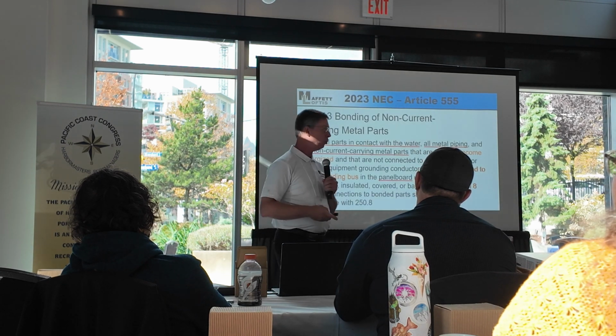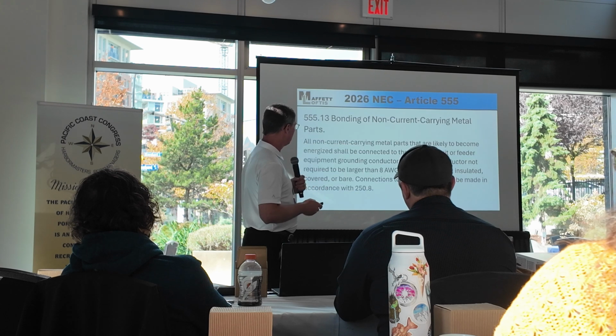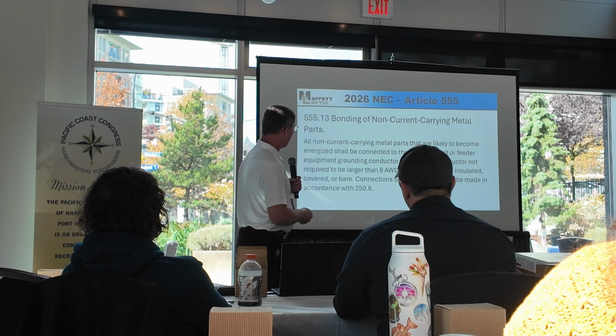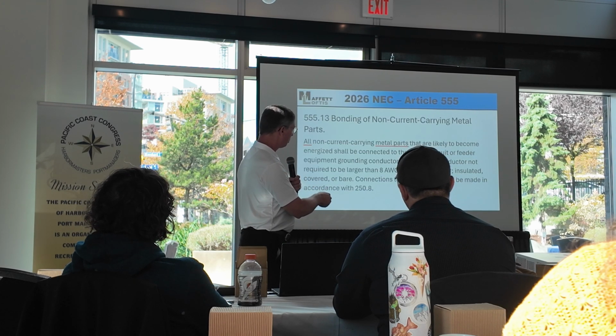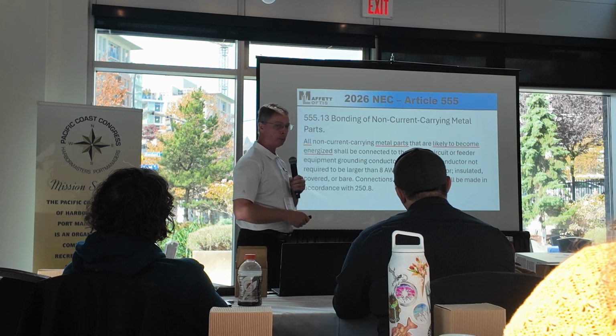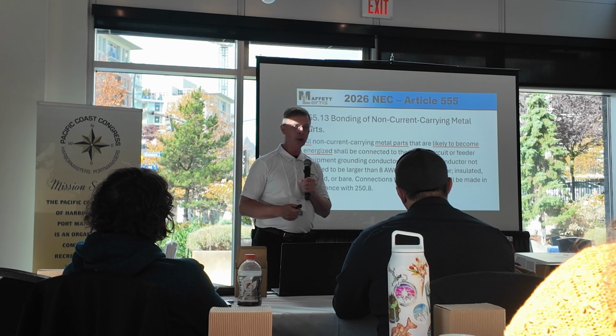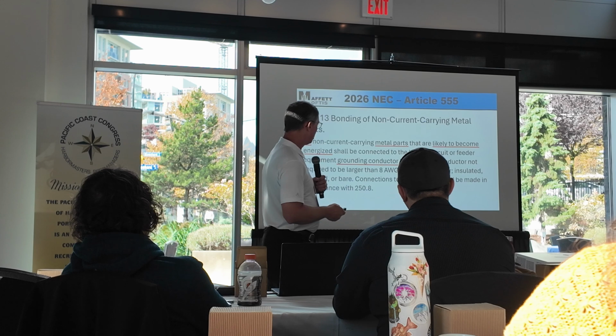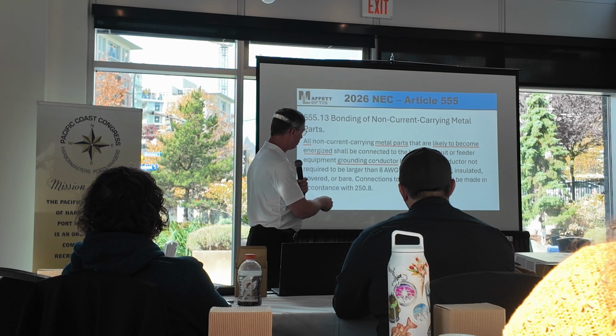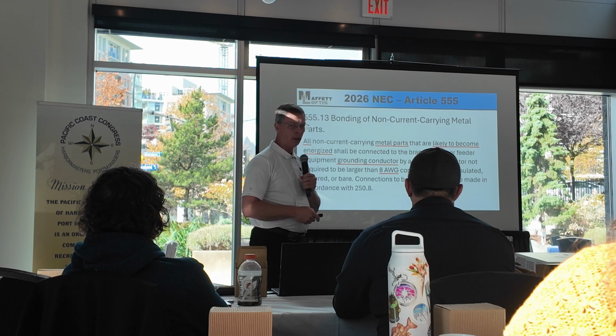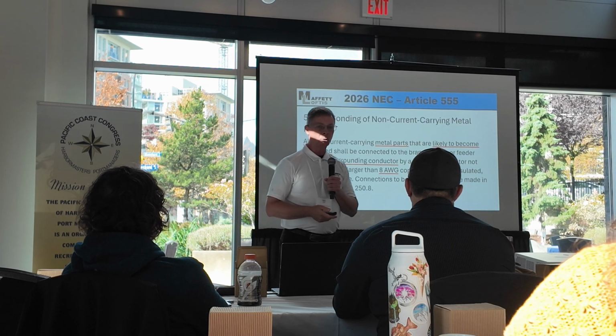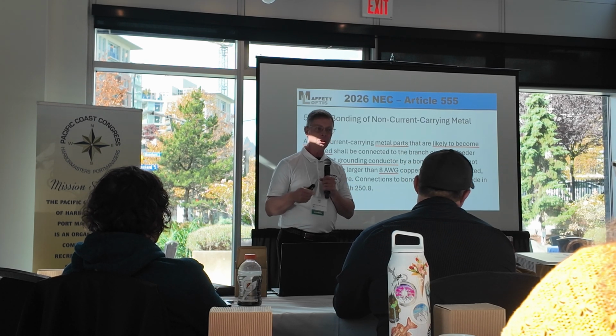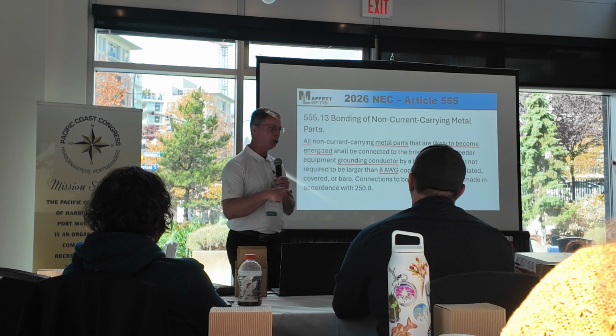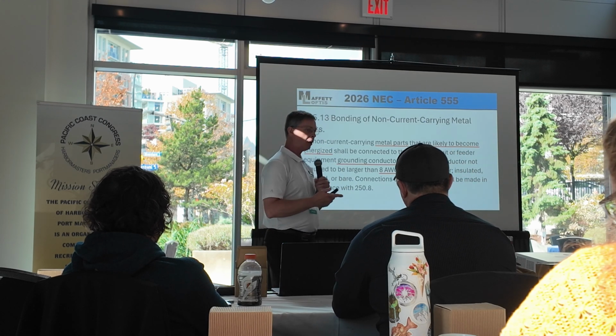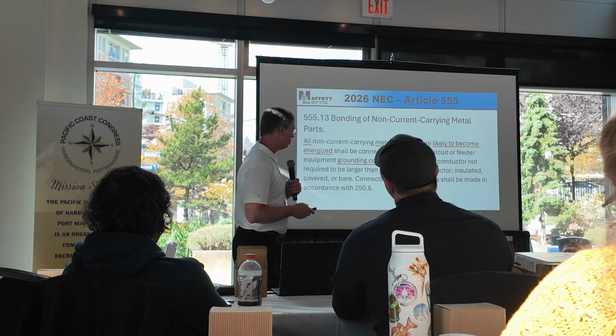So I submitted a public input, and this is what the 2026 says. Basically, it says all metal parts that are likely to be energized, period. If they're likely to be energized, then they'd be bonded to the grounding conductor, but it doesn't have to be greater than number 8. So that makes a lot more sense to me, and it has the intent of what the code making panel wanted to do in 2023. So we're trying to clear up and clarify some code issues there.